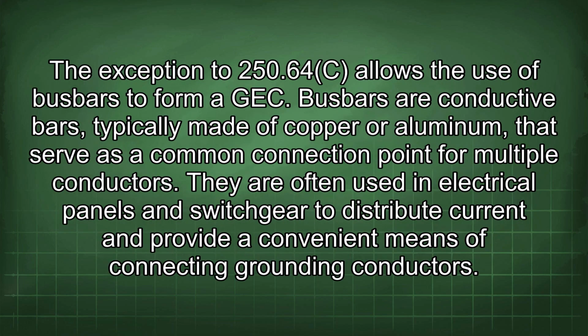The exception to 250.64(C) allows the use of busbars to form a GEC. Busbars are conductive bars, typically made of copper or aluminum, that serve as a common connection point for multiple conductors. They are often used in electrical panels and switchgear to distribute current and provide a convenient means of connecting grounding conductors.